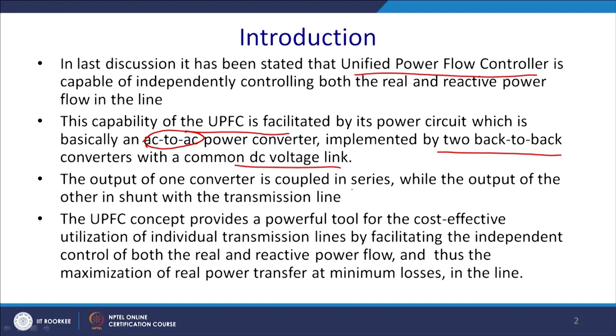The capability of the UPFC is facilitated by its power circuit, which is basically AC to AC power conversion. It takes power through the shunt path and injects power to the series route in case of the sag condition, and vice versa in case of the swell condition. This is implemented by two back-to-back converters with a common DC link.